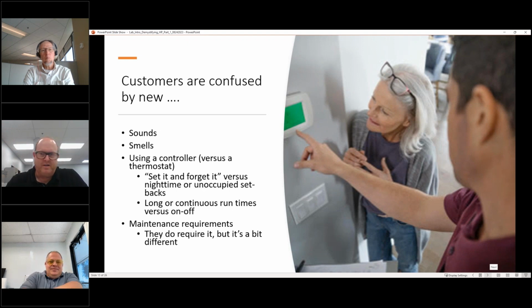That is different than a traditional heat pump where they got this thing on the wall and it says that's 68 and it's kind of making a temperature to that specific thing. Now there are ways to actually do that, so that's what I said typically, but still, people will go to Walgreens and get a thermometer and say, I'm sitting in my chair and it says it's 70, 69 right here, but that unit says it's 72. And that's because it's monitoring the temperature of the air coming back to itself. So that's just not bad or good. That's just how it is. So it's a little different.